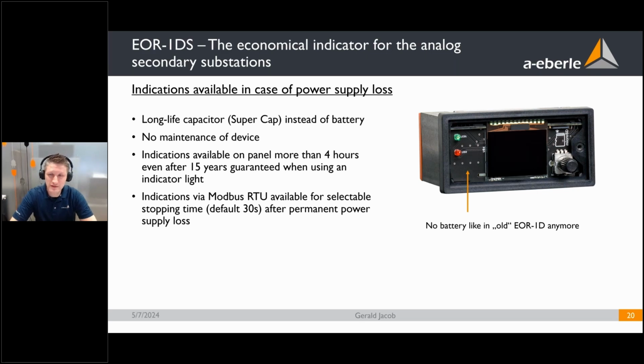Then there was a former device, the EOR-1D, that was equipped with an internal battery for indication of an earth fault or short circuit in case the supply voltage was interrupted. We always had discussions about maintenance intervals and so on. So we decided with the EOR-1DS, the actual device, that we will not use a battery anymore, but a supercap, a long life capacitor, inside the device. So you don't have to take care of the maintenance of the device.